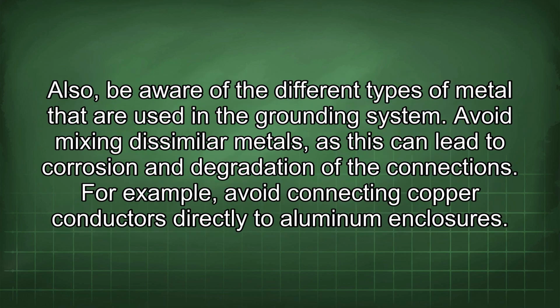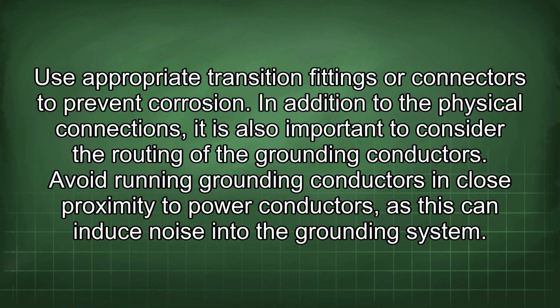Also, be aware of the different types of metal that are used in the grounding system. Avoid mixing dissimilar metals, as this can lead to corrosion and degradation of the connections. For example, avoid connecting copper conductors directly to aluminum enclosures. Use appropriate transition fittings or connectors to prevent corrosion.